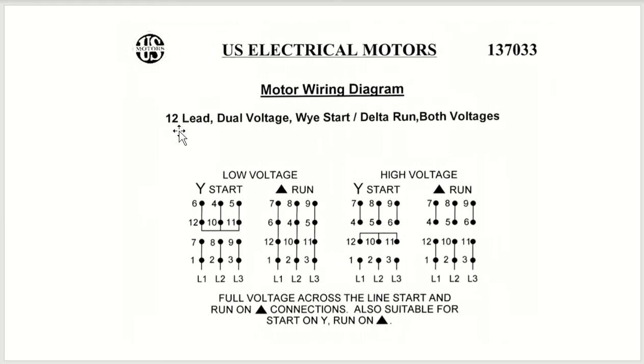If you do have a 12-lead motor, dual voltage Y start delta run motor, this is what you'll typically see for the connection diagram, and you're thinking, well, I can only have 6 leads. How do I use a 12-lead motor and only end up with 6 leads to do the Y delta starting? Well, in this configuration here, your combination of 6 and 12, 4 and 10, 5 and 11 would actually be your 6, 4, and 5. Your combination 1, 7, 2, 8, 3, 9 would become your 1, 2, and 3. So that would be your 6 leads. When you started in the run configuration, you can see that 6 and 12 are still connected to each other, 1 and 7 are still connected to each other. So that's how you do it with their low voltage.